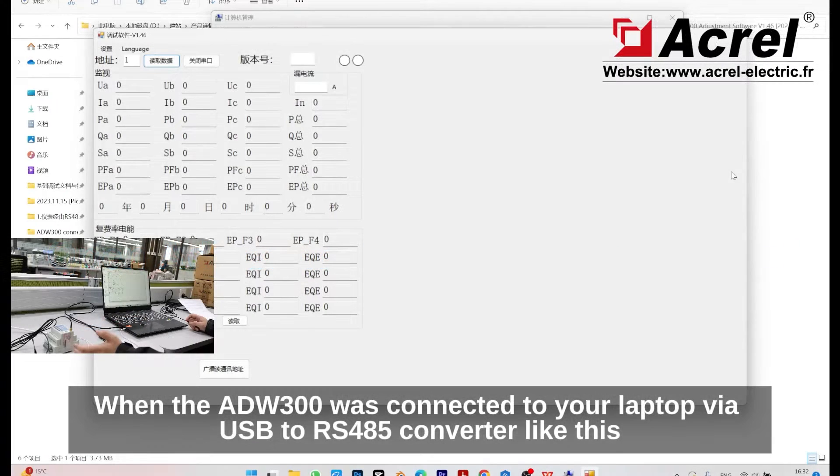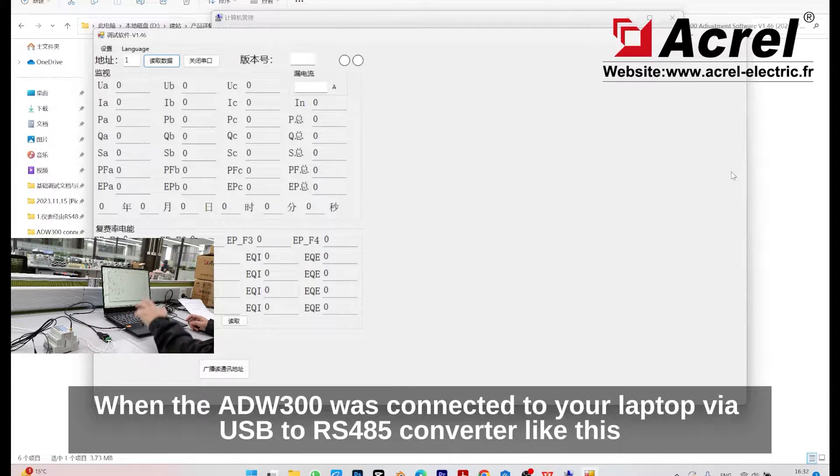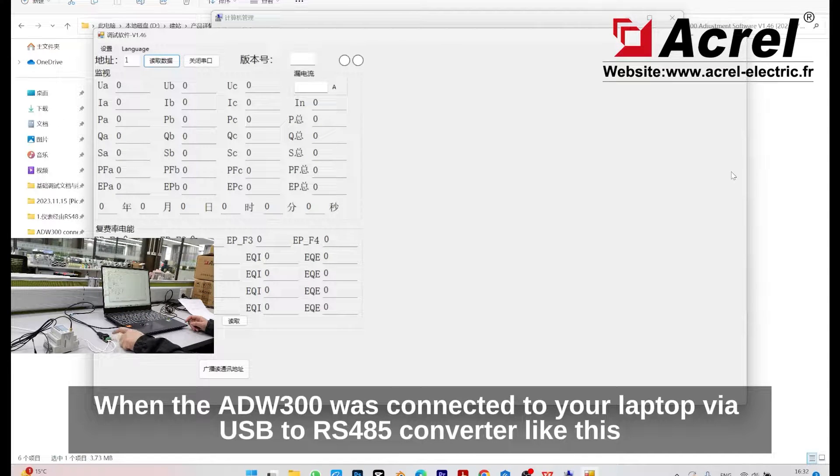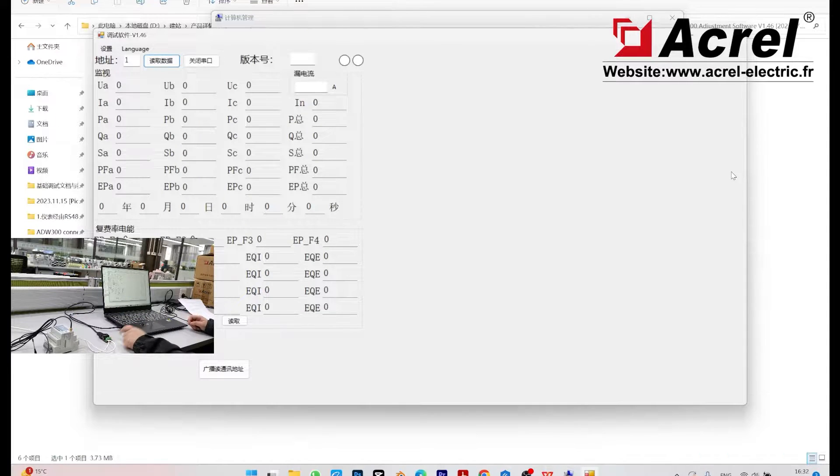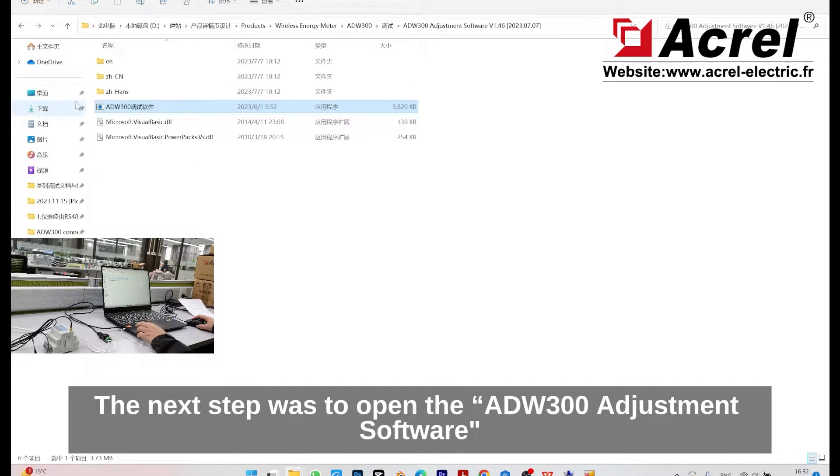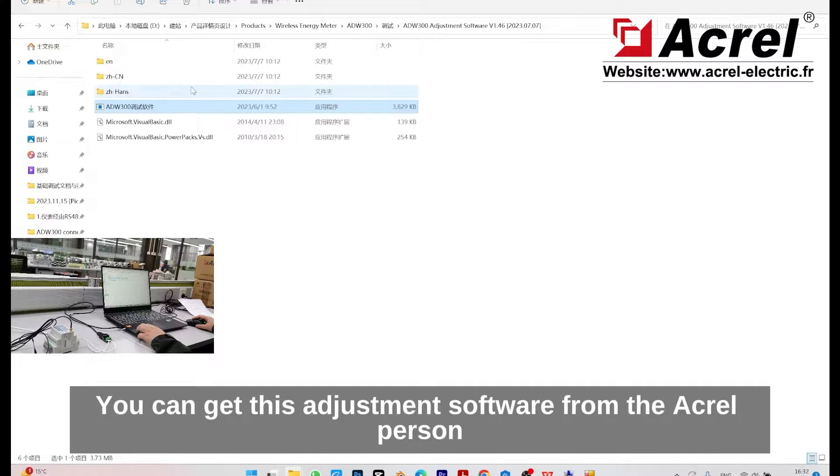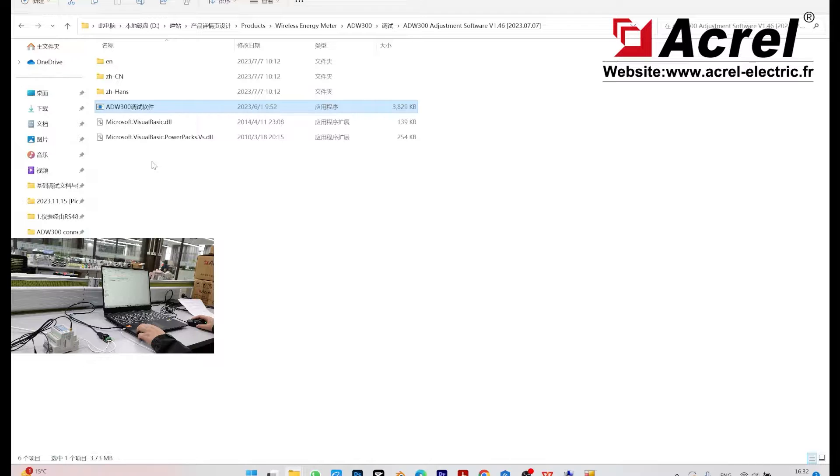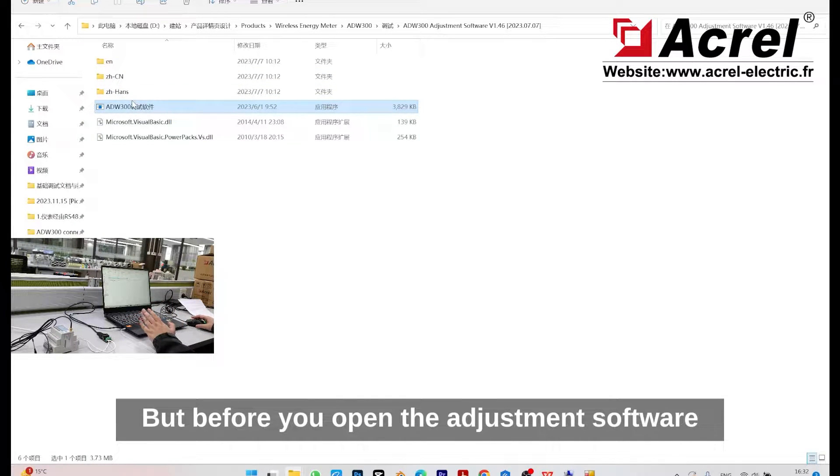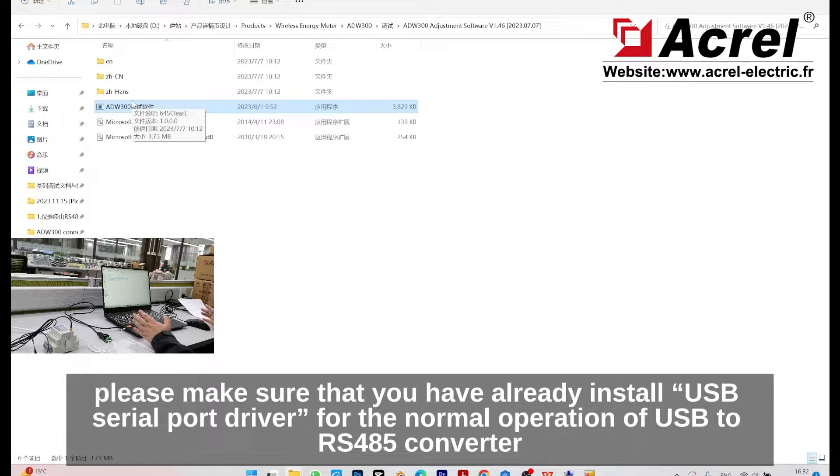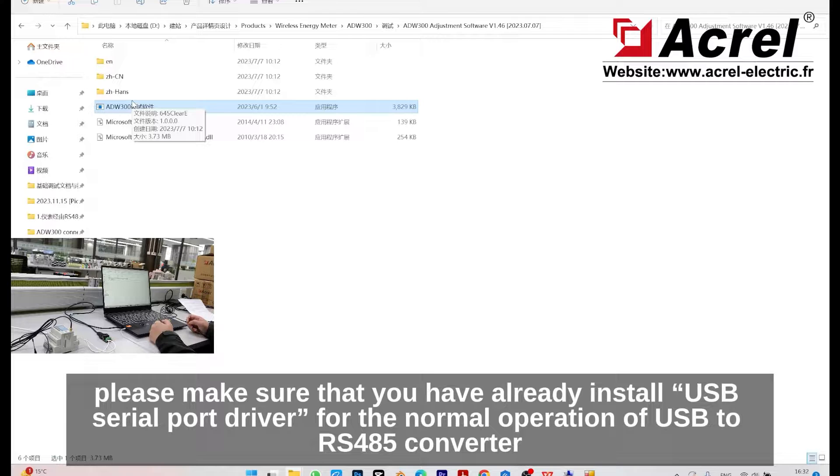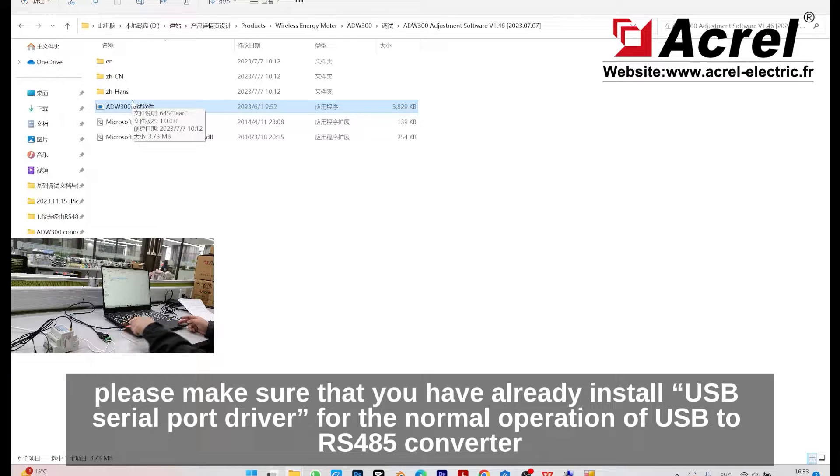When the ADW300 is connected to your laptop via USB to RS485 converter like this, the next step is to open the ADW300 adjustment software. You can get this adjustment software from Acrel. Before you open this software, please make sure you have already installed the USB serial port driver for normal operation of the USB to RS485 converter.